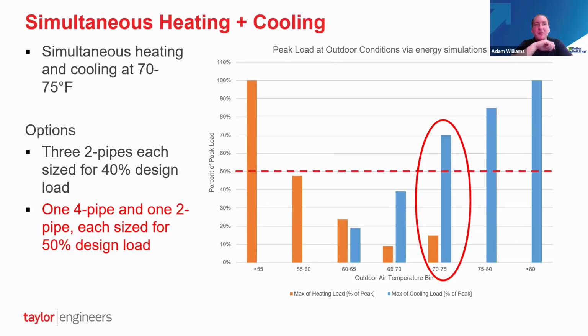So on our job, we did some energy modeling to look at both the peak heating, the peak cooling, and also the simultaneous loads at a mild 70-degree outdoor air temperature. And we found that although the simultaneous loads don't happen that often, they're generally pretty high. They're high enough to have us consider doing one heat recovery machine to handle those simultaneous loads and provide efficient operation during that, and one 2-pipe unit for affordability reasons. So that's pretty much the job, and I'll wrap it up.